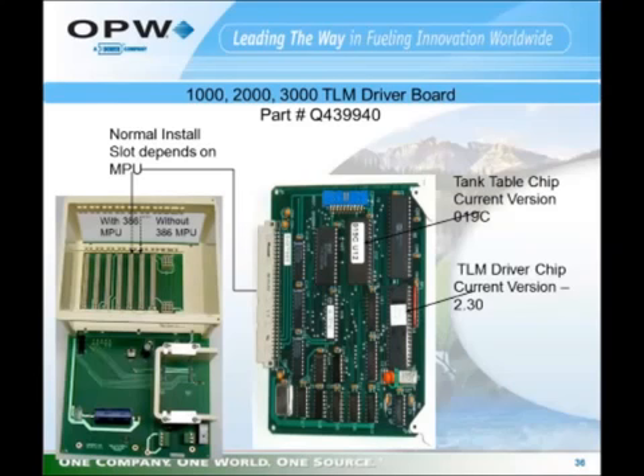The 2.30 chip on the TLM driver board will support all of the original EECO Q0400 probes. If an original EECO Q0400 probe fails, that probe is no longer manufactured. It has been replaced by the TLMB probe. In order for the EECO 2000 to interface to the TLMB probe, that TLM driver chip must be upgraded to the version 4.3 software to support that probe. It is also backwards compatible to the original probes. If you have to replace a probe and you order a TLMB probe, you will receive with each probe a 4.3 version software TLM driver chip to be used on the TLM driver board.